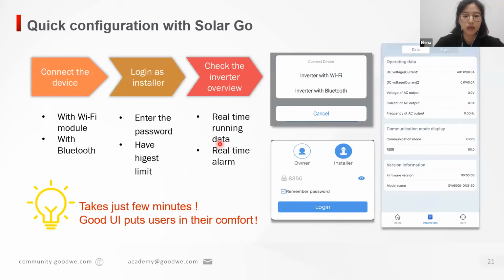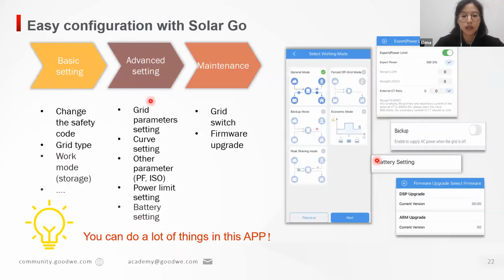You can connect the device locally via Wi-Fi or Bluetooth. And then the installer can log in as installer role, and only the installer has the authority to do some setting for the inverter. So in the parameter page, you can see some detailed real-time running data and real-time alarm information. Then the installers can do some basic setting, such as change the safety code, choose the grid type, and the work mode for the storage inverter.